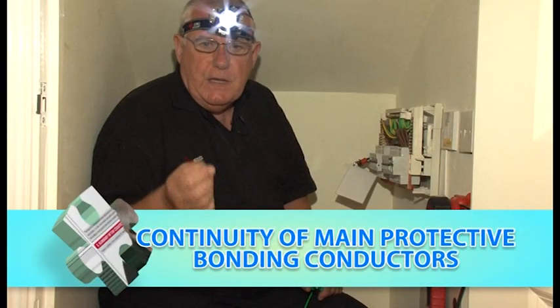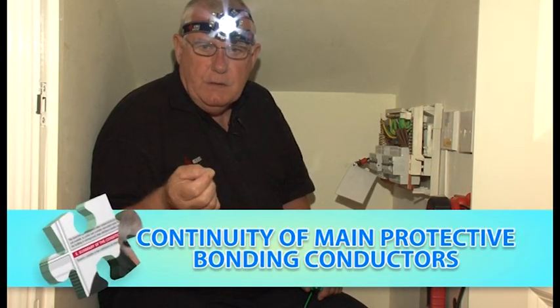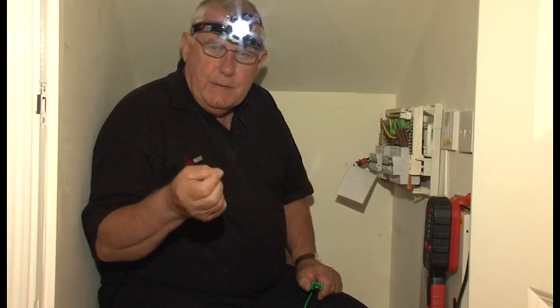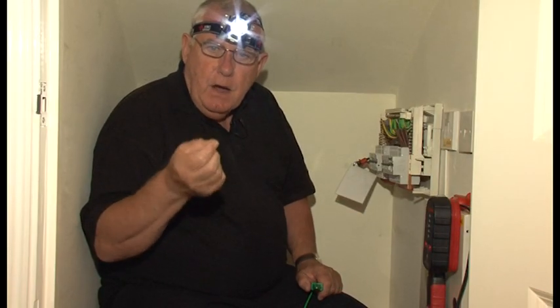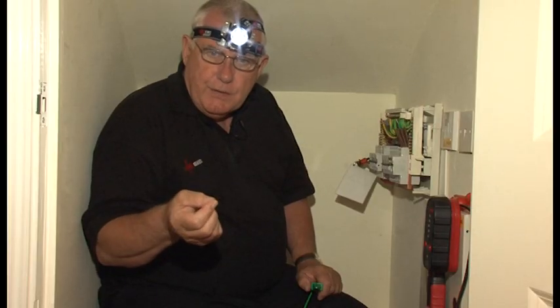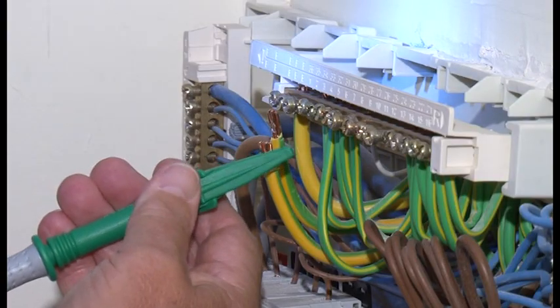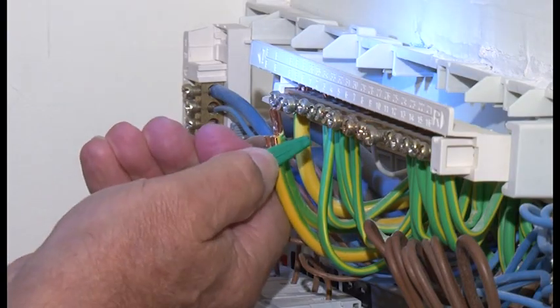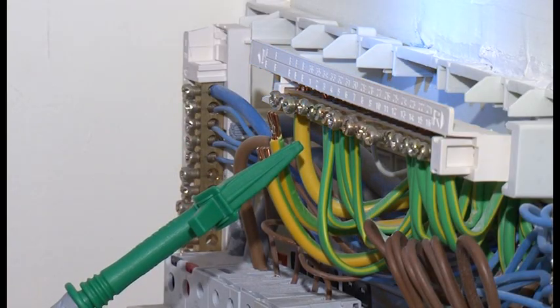I've verified the CPCs exist for accessories. I now want to verify the continuity of the main protective bonding conductors. Again, I'll be using the R2 test method. To do this, Tony will leave the conductors disconnected at the MET and connect the R2 wander lead, which has been nulled out on the test instrument. So first to the water.